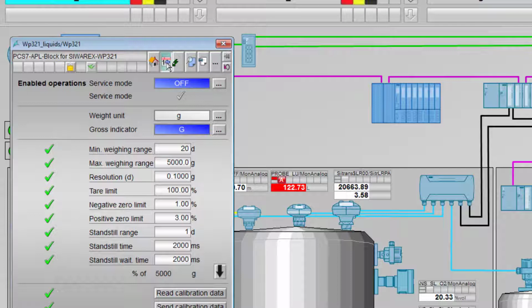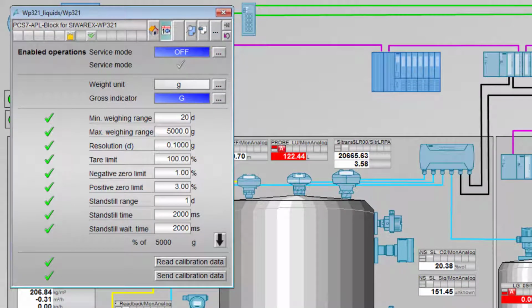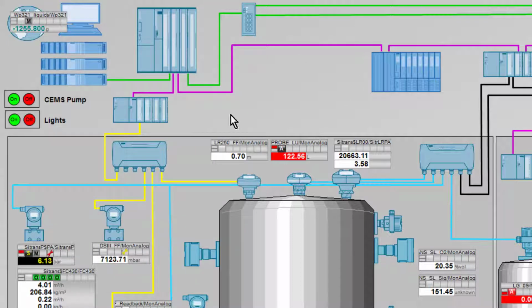So the really nice thing about PCS7 is, unlike TIA portal, where I've got to be careful when I add multiple of these devices, I've got to start copying function calls and things like that, PCS7, I just keep dragging that CFC into my project, generate the graphics, PCS7 sorts everything else out for me. So it's a lot more user friendly in that way, which we expect from a top end DCS. So the only thing I need to do is to position this icon on my vessel.